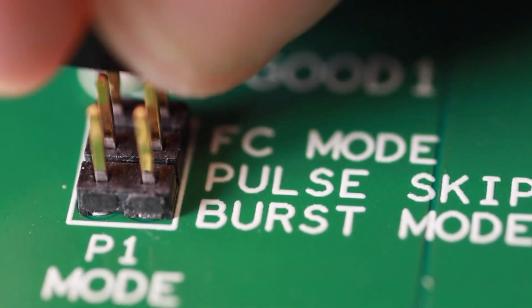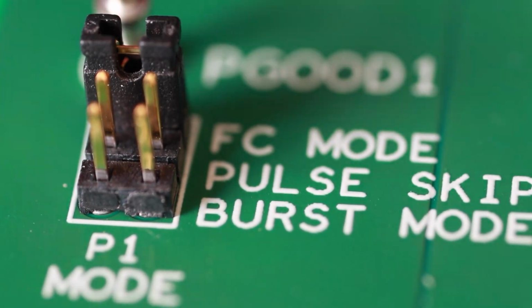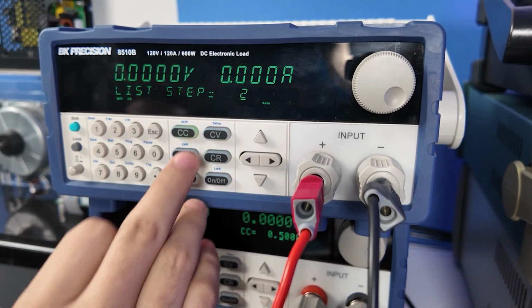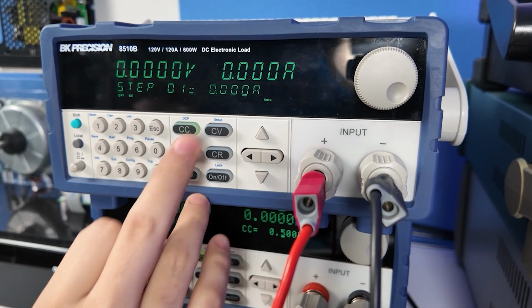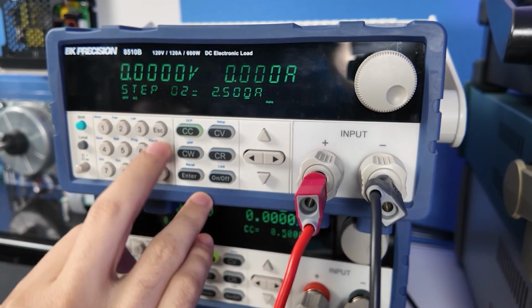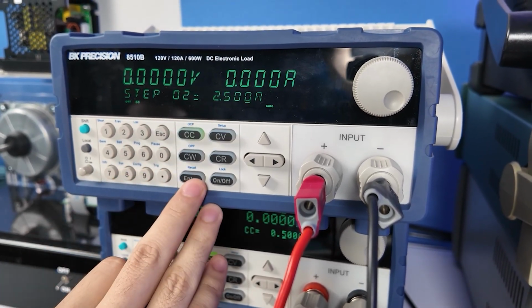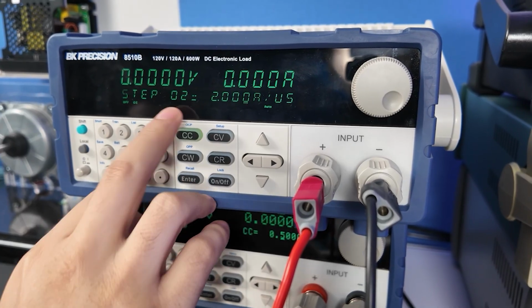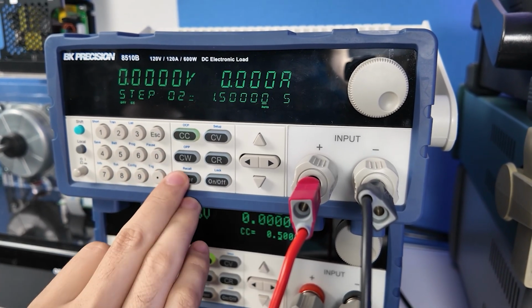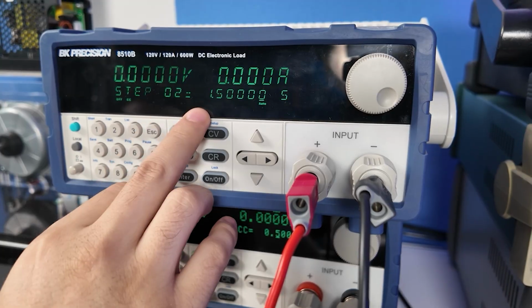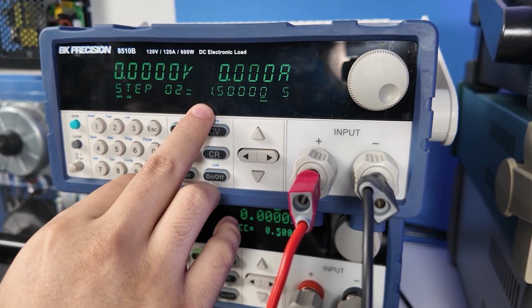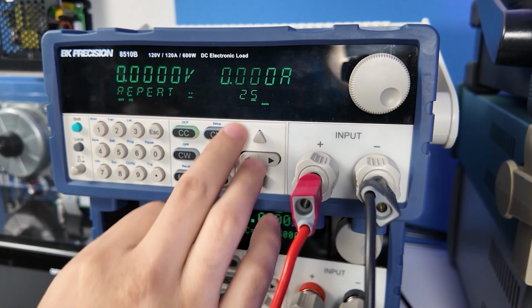Next, we'll do a dynamic load test in continuous mode. For this, make sure you change the P1 jumpers as shown. We'll program a 2-step list. Step 1 at 0 amps, Step 2 at 2.5 amps, and set the slew rate at 2 amps per microsecond. The dwell time is set to 1.5 seconds and set the number of repeats to 25 times, so that we can have enough time to capture our transients.